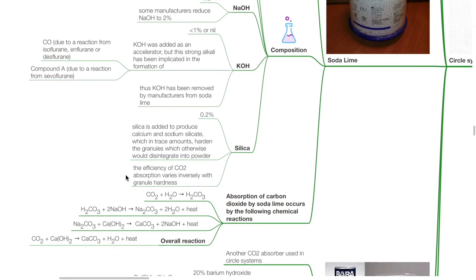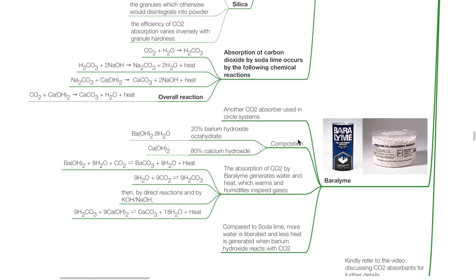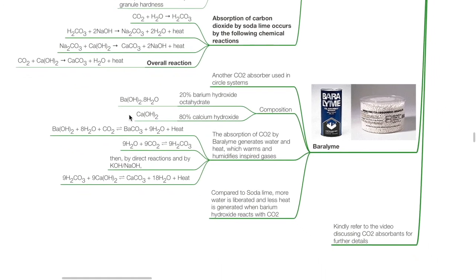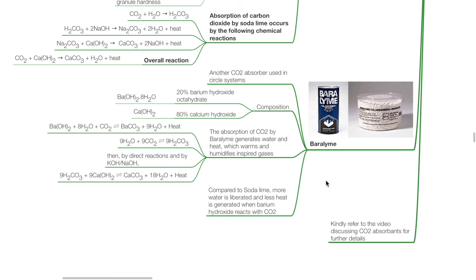Absorption of CO₂ by soda lime occurs by the following reactions: CO₂ + H₂O → H₂CO₃; H₂CO₃ + 2NaOH → Na₂CO₃ + 2H₂O + heat; Na₂CO₃ + Ca(OH)₂ → CaCO₃ + 2NaOH + heat. The overall reaction is: CO₂ + Ca(OH)₂ → CaCO₃ + H₂O + heat. Baralyme is another CO₂ absorber used in circle systems, composed of 20% barium hydroxide octahydrate and 80% calcium hydroxide. Compared to soda lime, more water is liberated and less heat is generated when barium hydroxide reacts with CO₂.